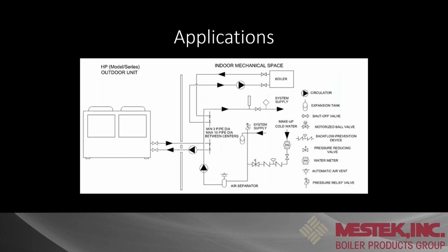And then I just wanted to show this one last one, which is basically a primary, secondary. In this particular one, we've got one heat pump pumping towards that. But then we have tied in a boiler, whether it's an injection loop or just a backup boiler, or even an existing boiler plant that's there. We're looking to just tee in our heat pump onto that main loop and do what's needed there to reduce the carbon footprint.